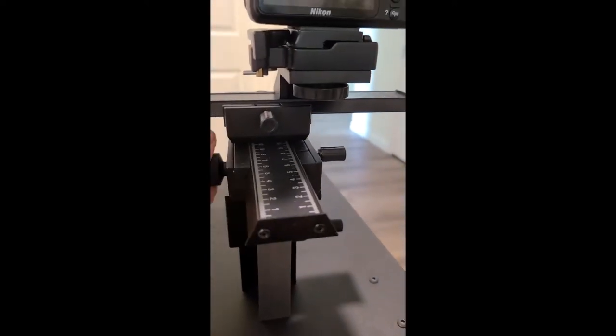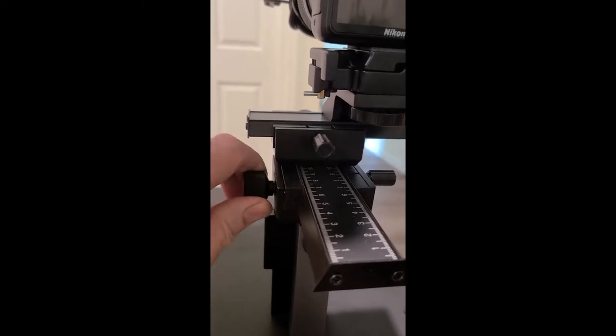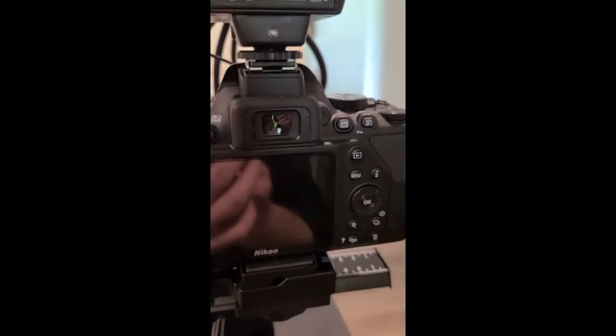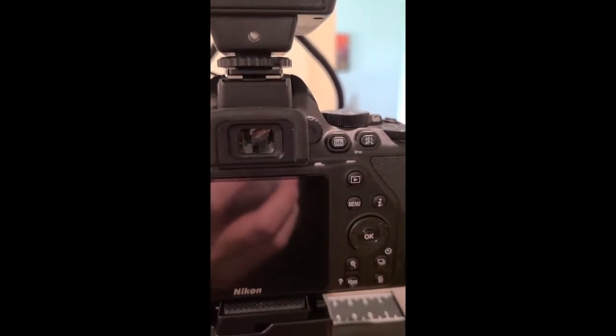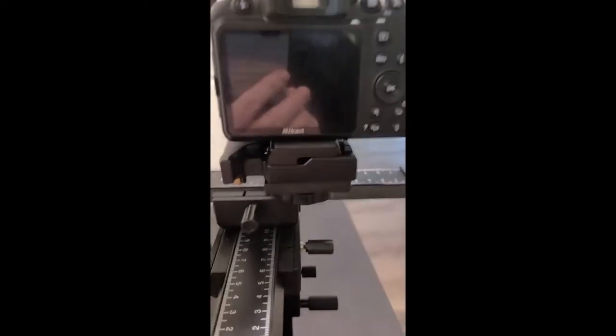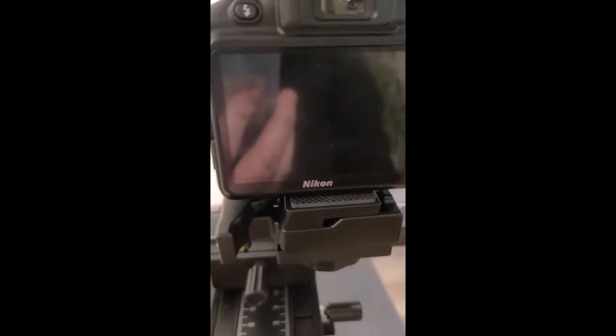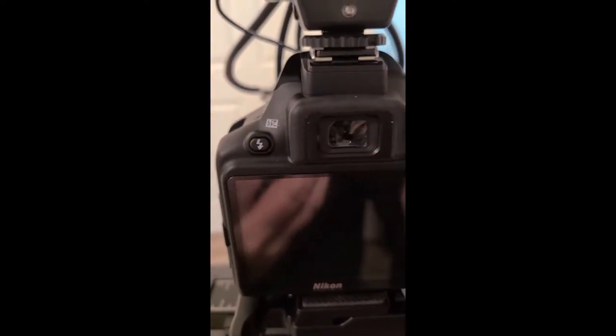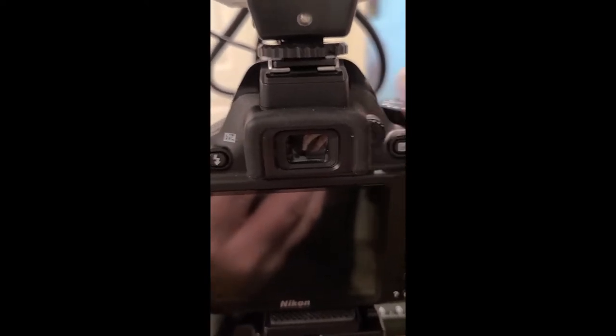As you're focusing on the person's irides, you're going to use this little knob on the side — forward and back. This is the diopter. You're going to look through here at the person's eye while focusing in and out, and when you get it perfectly in focus, you click this button up here to take the picture. Everything flashes and it'll show up on the display so you can see what it looks like.